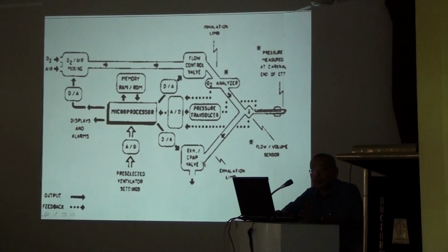What is the analogy behind it? I have explained the analogy of the oxygen sensor here. Now I am going to the flow sensor analogy. Why has ISO given a directive to attach the flow sensor at the exhalation port? Now the flow sensor is here. What is the work of the flow sensor? The flow sensor will pick up the velocity of the gas. And this pickup will be converted to a numerical figure as a quantum of air.